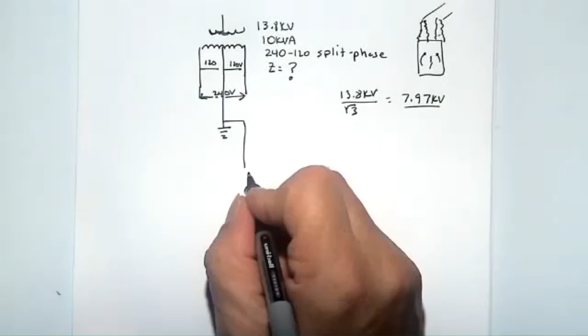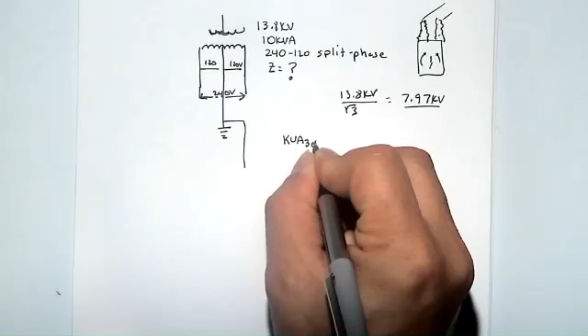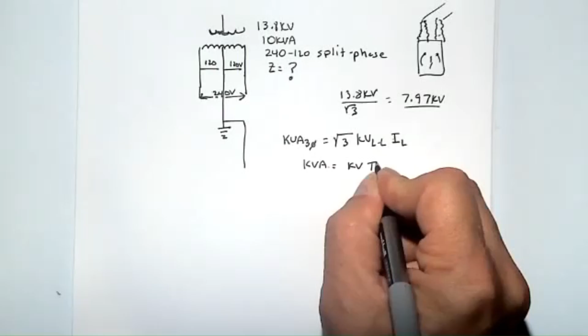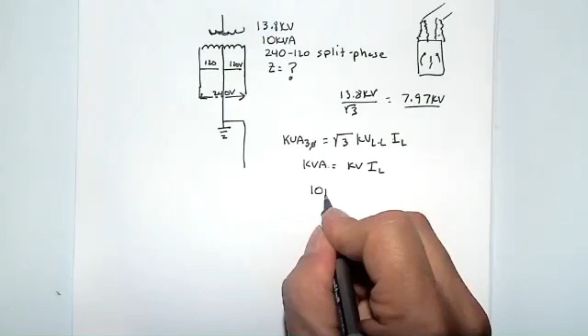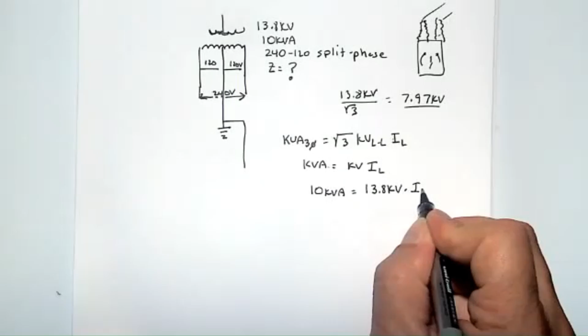So what are we going to calculate? The breaker that's in your home is typically a two-pole breaker connected on that 240 volt line, so we're going to calculate based on the 240 volt. Instead of using kVA three-phase equals square root of 3 times kV line to line times I line, we're just going to say kVA equals kV times current. In this case, we know the kVA, which is written on the side of the transformer, is 10 kVA, and the voltage on the primary is 13.8, so that'll give us our I primary, full load. Let's just calculate that out.